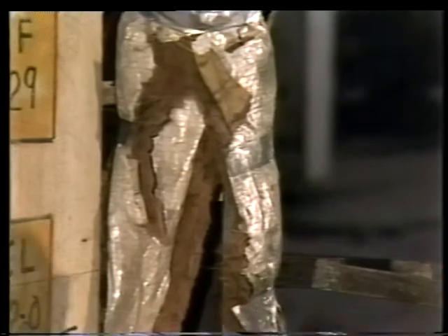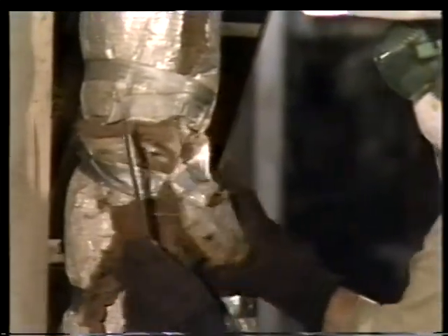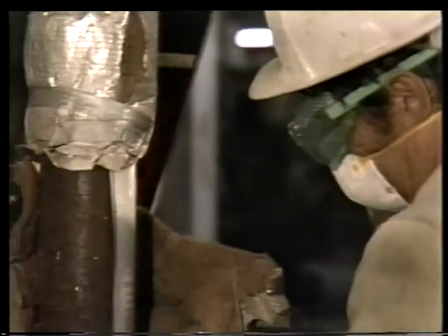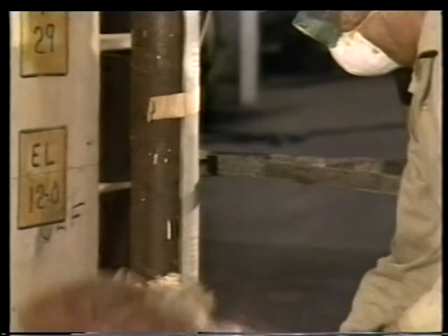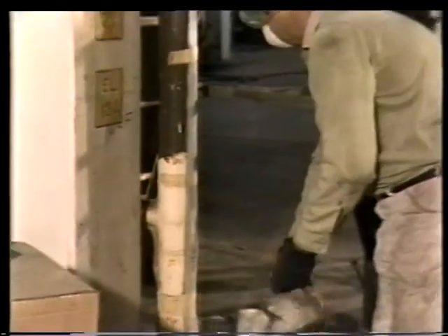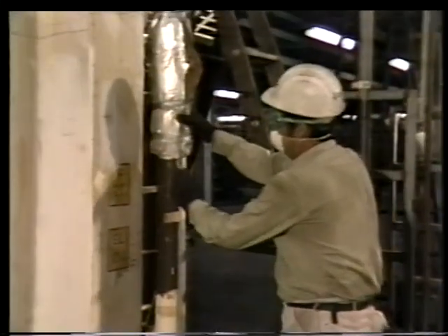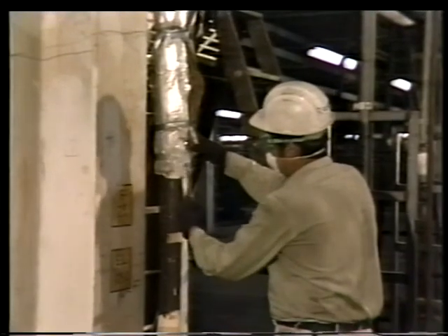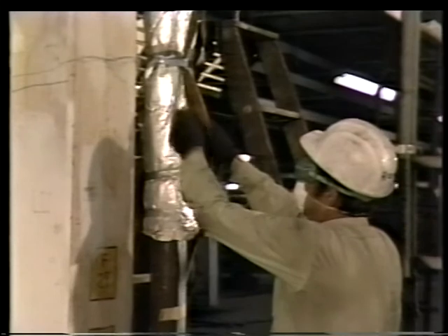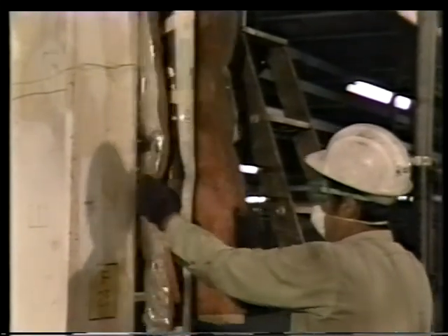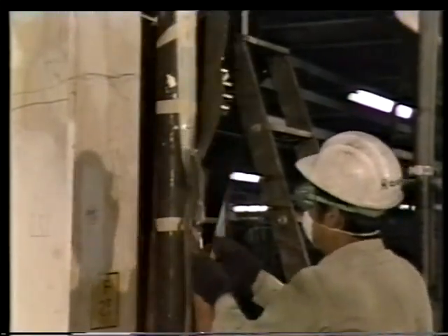As you can see, this insulation is badly in need of replacement. It's easily removed by cutting the tape with a sharp knife. But be careful. The flat plastic element is the electrical heat tracing. When you're working on runs that are heat traced, be careful not to damage the tracing with your tools. It could be a shocking experience. Now, even though it's tagged out, when it's turned on again, a damaged heating element can cause real problems.